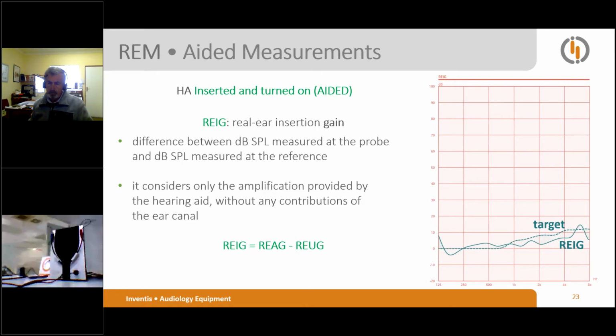The aided curves described so far represent the gain contribution provided. If the operator was interested in quantifying the contribution provided by the hearing aid only, simply select the open insertion, and the real ear insertion gain measurement will be acquired. We will see that the usability of Maestro software is very high. Maestro has a very user-friendly interface. So if the user wants to acquire a real ear insertion gain, it is just necessary to push a button. And that's it, press one button. If you want to acquire a real ear occluded gain, another button. It is very easy to use. We will see it later.